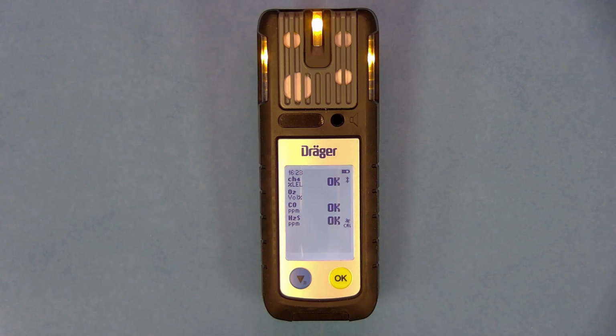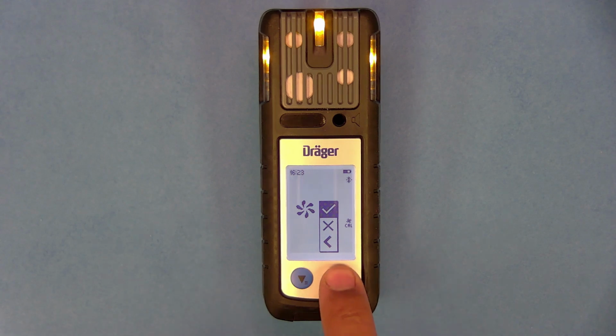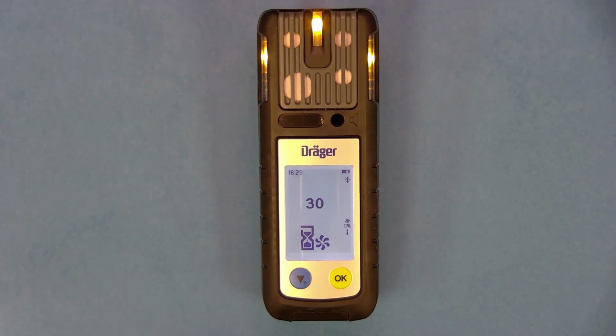You'll get OKs on all 4 sensors, and at that point your zero calibration is done. You can push the green button one more time to access the check mark. And once you hit the OK button one more time, it'll save that fresh air calibration.